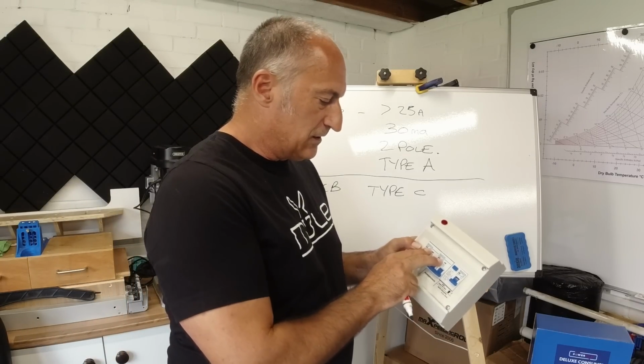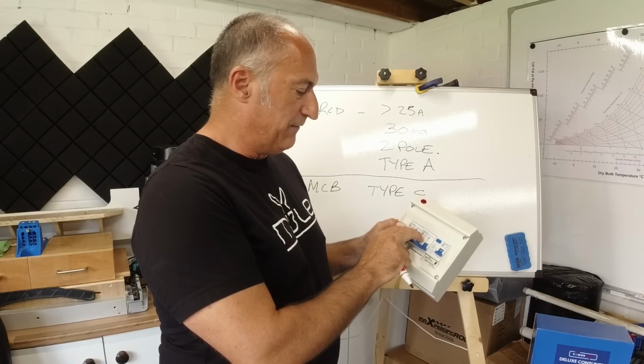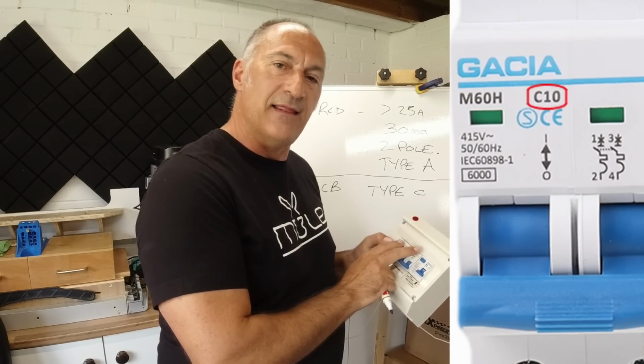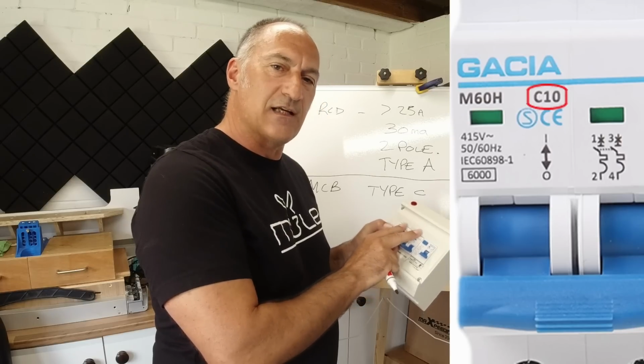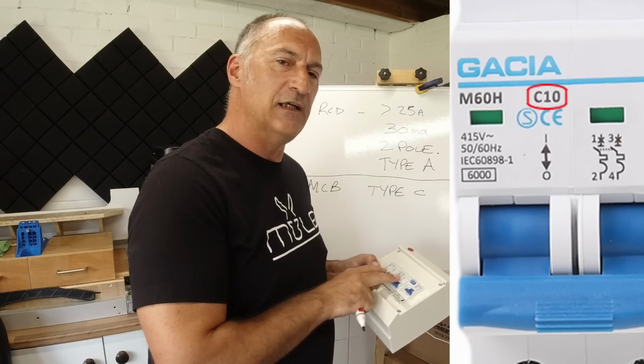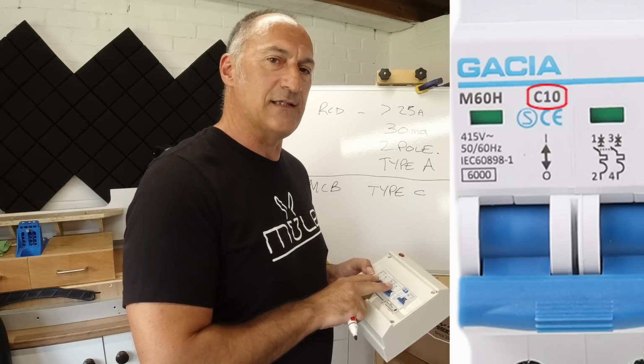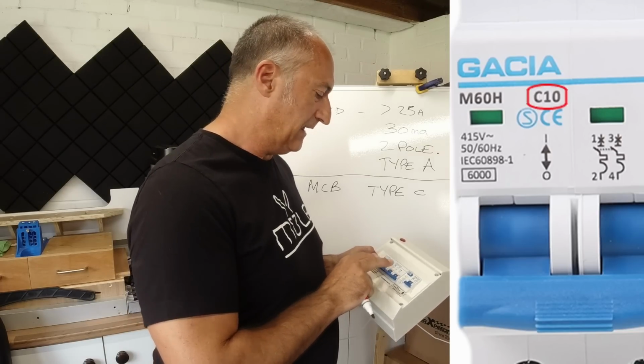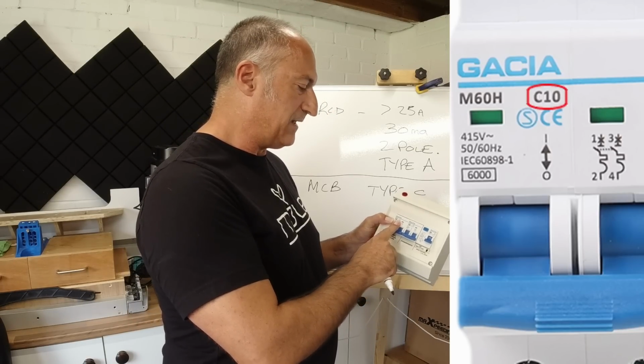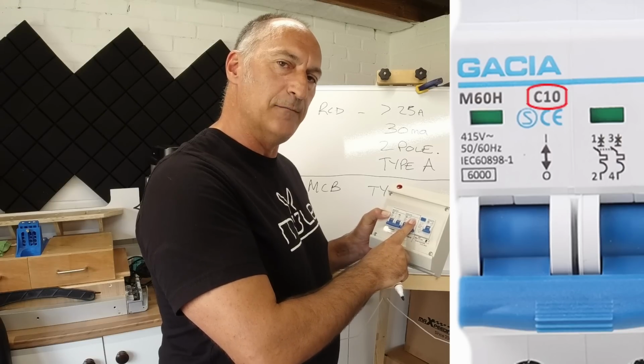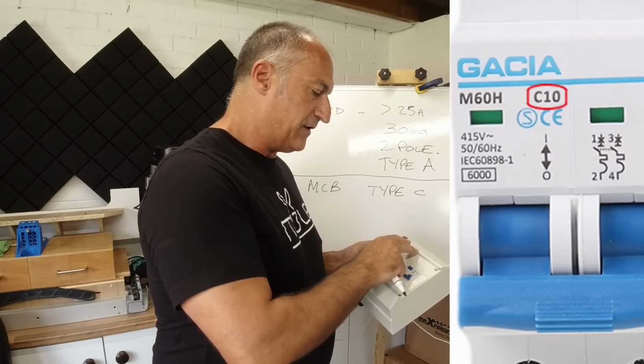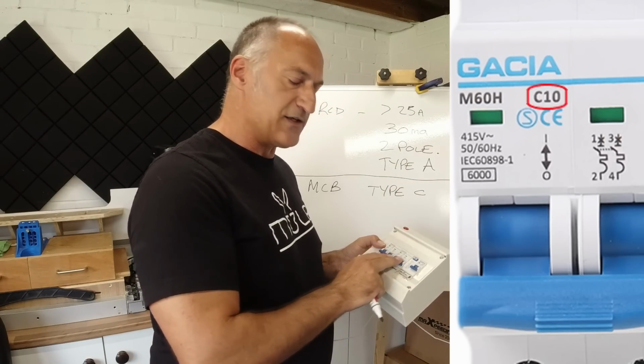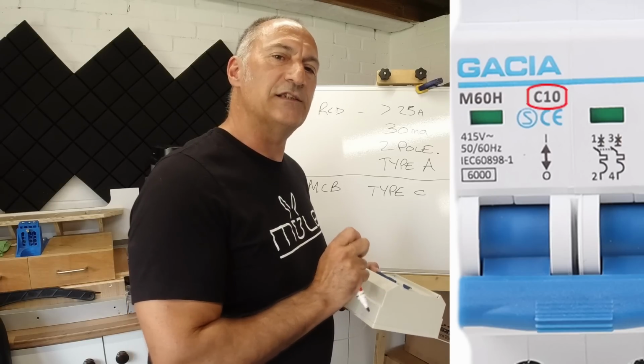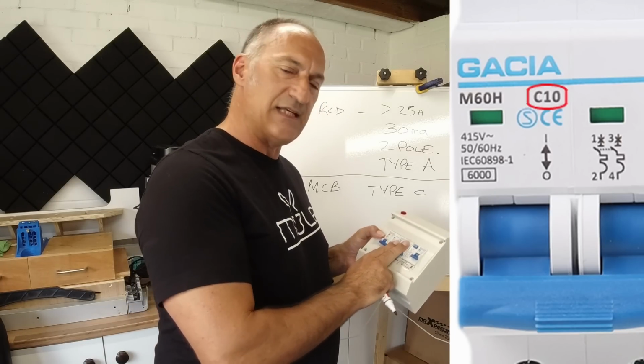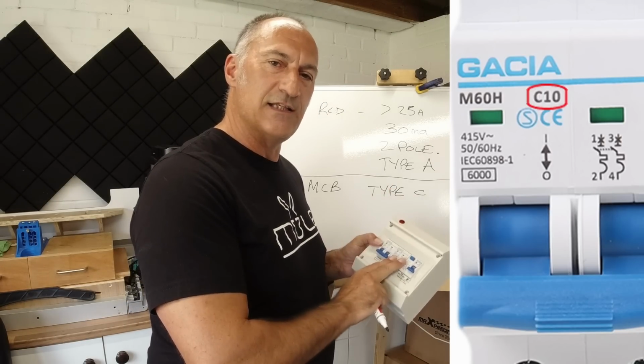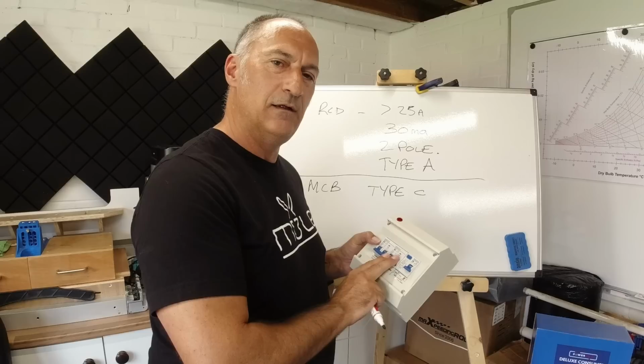Then you'd need to look at the number on here. We've got 6 and 10, and that's amps. That relates to the current that will flow through this device, so it's like the fuse rating of each device. In this case we've got a 6 amp breaker and a 10 amp breaker. If there's an overcurrent in excess of 10 amps, after a certain amount of time the bimetallic strip will heat up and this MCB will trip out.